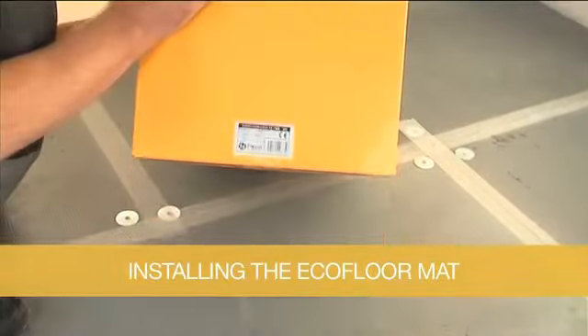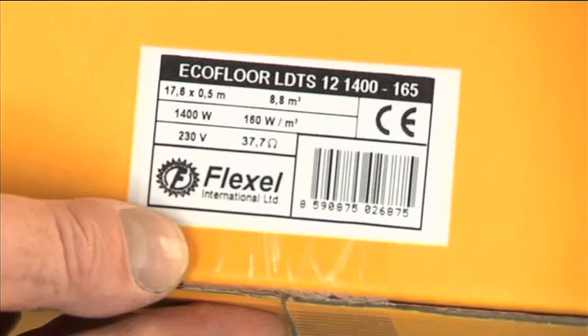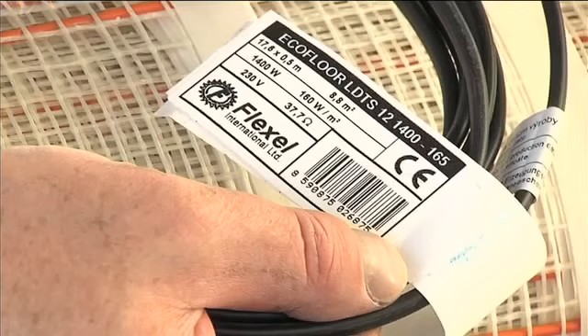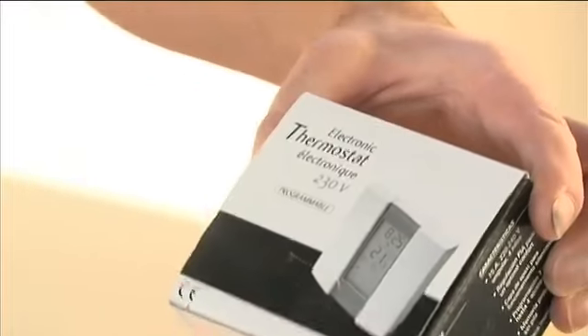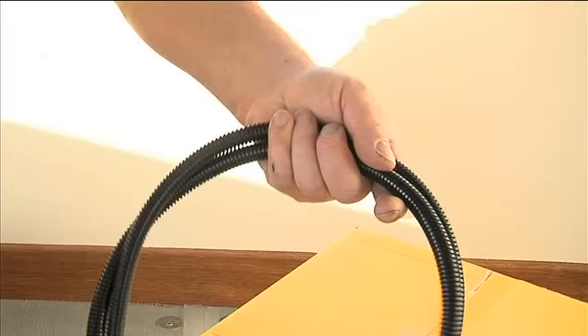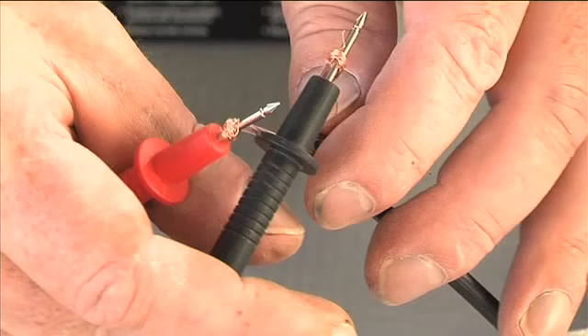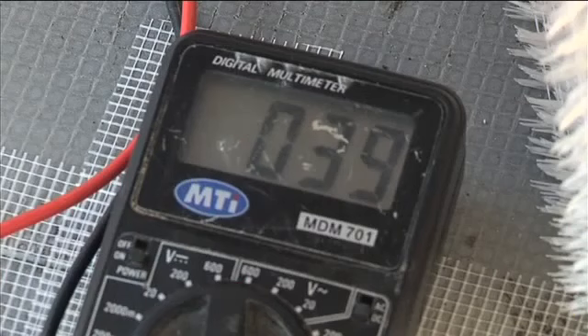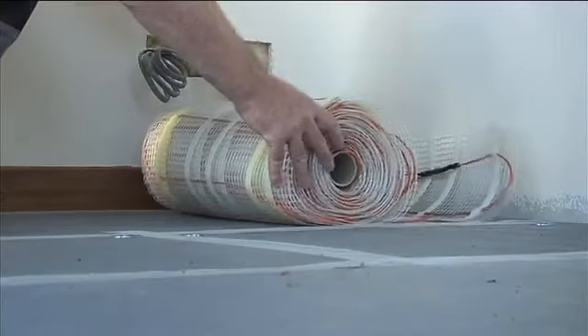Before commencing the installation of the mat, please confirm that you have the correct mat size, a thermostat with floor probe, and a length of protective conduit for the floor probe. It is important to check the resistance of each mat against the label value before commencing installation to ensure that it has not been damaged in transit. It is good practice to regularly recheck the resistance during the installation process to ensure the mat has not been damaged during installation. The mat should be unrolled as planned.